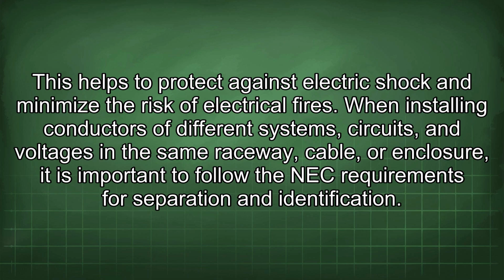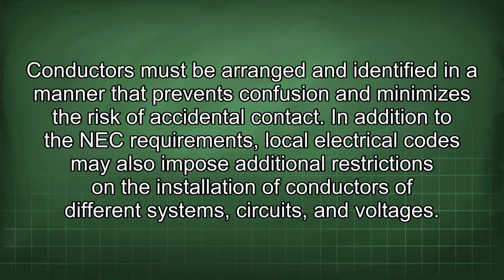When installing conductors of different systems, circuits, and voltages in the same raceway, cable, or enclosure, it is important to follow the NEC requirements for separation and identification. Conductors must be arranged and identified in a manner that prevents confusion and minimizes the risk of accidental contact. In addition to the NEC requirements, local electrical codes may also impose additional restrictions on the installation of conductors of different systems, circuits, and voltages.